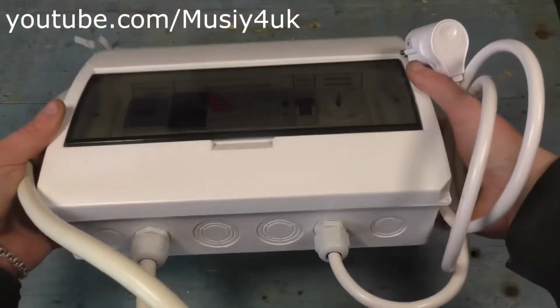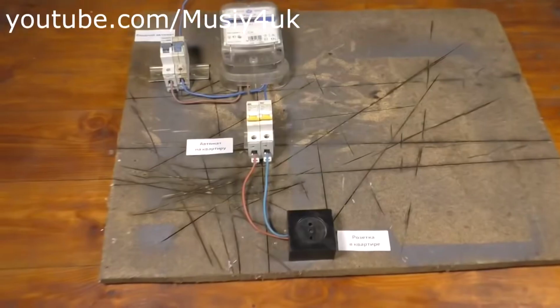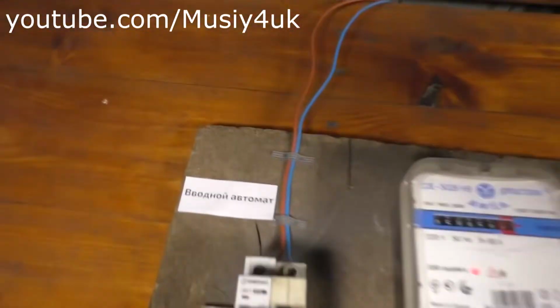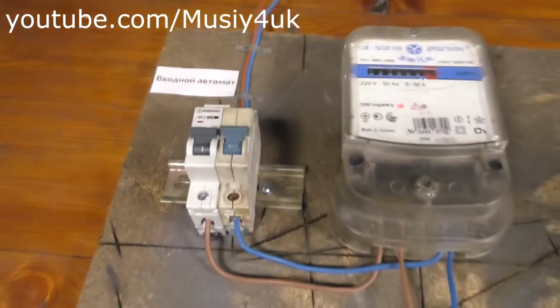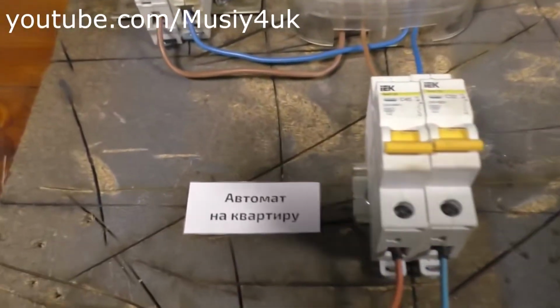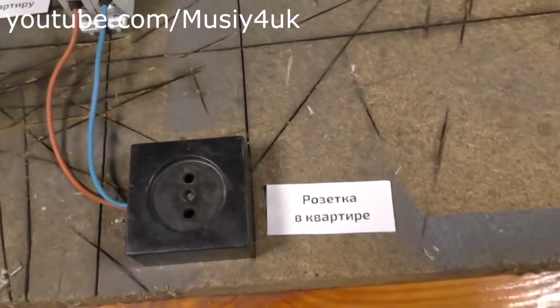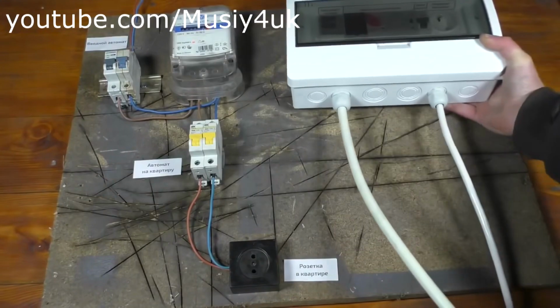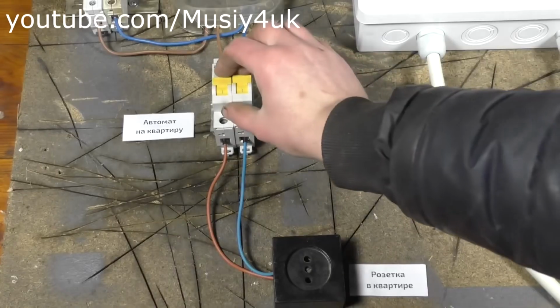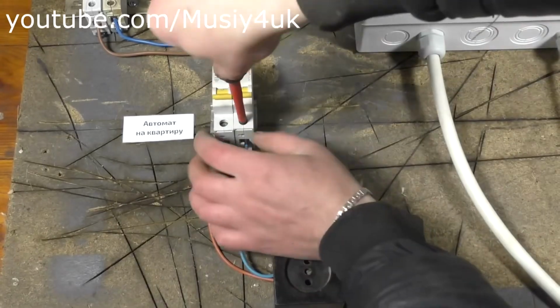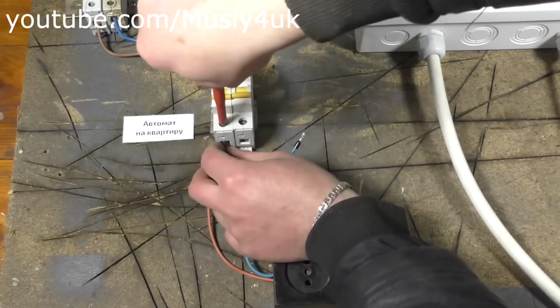Next, I'll show you how to connect it to your apartment properly. Here we see a typical wiring diagram. There is a main circuit breaker before the meter, and after the meter there is a breaker for the wiring. In your apartment, you need to install the automatic transfer switch panel somewhere nearby, then turn off the breaker after the meter and disconnect the apartment wiring from it.